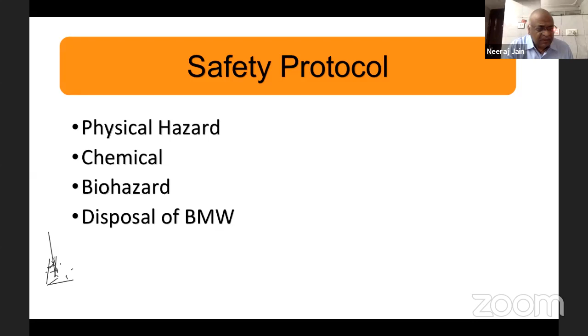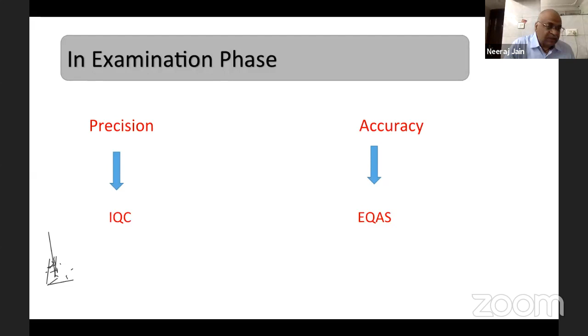Sometimes people get confused. When we are regularly participating in IQC, is it essential to participate in EQAS? See, with IQC, we get information about precision, how close our results are to each other. With EQAS, we get information about accuracy, how close our result is to the true value. Both are important, and these are requirements of ISO 15189 also. If you are going for accreditation and want to comply, this is a must. For internal quality control, how many levels you will run and how frequently you will run is decided based on your workload and distribution of work. And if the accreditation body has recommended something, at least you have to follow that. For this IQC, we shall have a documented procedure, and we have to implement it as per our documented procedure.